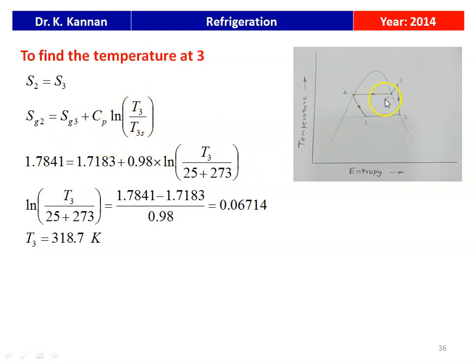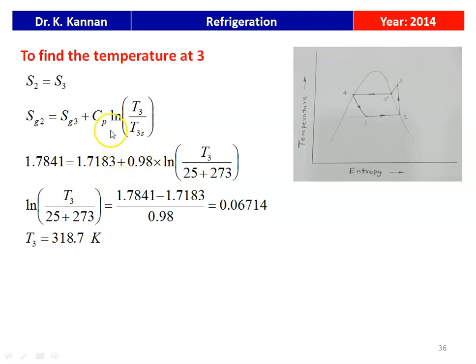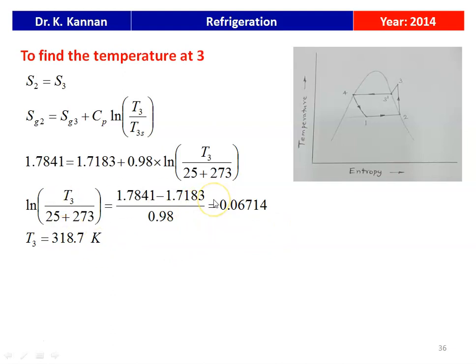We write: Sg2 equal to Sg3 plus Cp multiplied by the logarithm of T3 divided by T3s. For the given evaporator temperature, Sg2 equals 1.7841. For the given condenser temperature, Sg3 equals 1.7183, and Cp is 0.98. Rearranging, the logarithm of T3 divided by (25 + 273) equals (1.7841 minus 1.7183) divided by 0.98, which gives 0.06714.